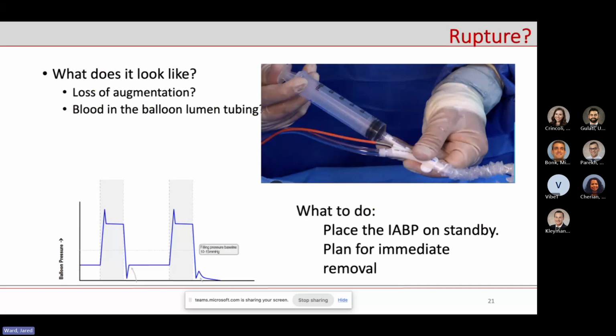The big things, and this is probably one of the ones that you're going to get caught on in a board exam, is what happens if it looks like there's a balloon rupture. In the balloon sheath and the helium sheath, remember these should be closed systems, right? The balloon inflates and deflates with helium, and there shouldn't be any blood in it. So if there's ever blood in the tubing, like on the bottom right of the image, or if you're looking at your balloon waveform and it's not coming back to baseline and it's showing a drop off in its baseline pressure, that would all be concerning that the actual balloon has been compromised. At which point you put it in standby and you've got to get it out, because it's just going to cause a ton of problems.